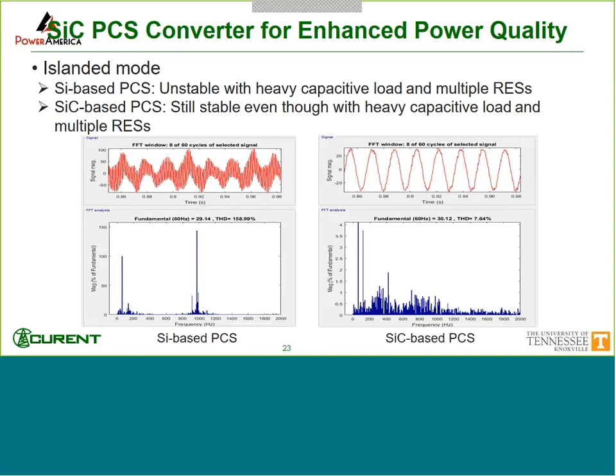For islanded mode and the microgrid, the PCS will not provide power, so it's just sitting there not doing anything. So you could use it as a stability enhancer. In this case, again, if we have some unfavorable load condition that does not match well with the battery or other energy sources or PV energy sources, and assuming those sources do not have the bandwidth to deal with it, our PCS converter would be able to help with the stability, as shown here. This is the silicon-based versus silicon carbide-based case.